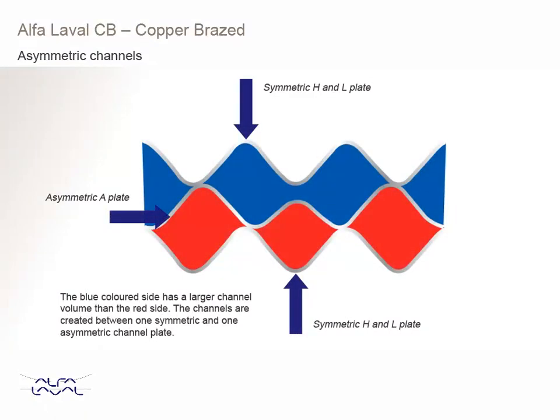For some of the Alfa Laval CB models, we have asymmetric channels. Asymmetric channels provide for better utilisation of the allowed pressure drop on both sides. This means that the channel volumes are different for the cold and hot sides. With this, you can optimise the heat transfer and thereby minimise the number of channel plates in the unit. Asymmetric plates are normally combined with a symmetric H or L plate.